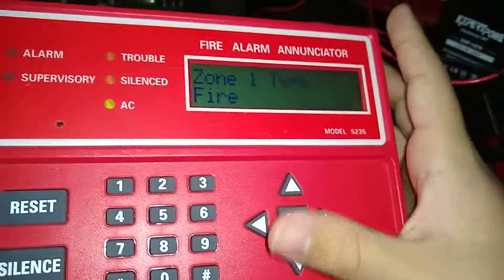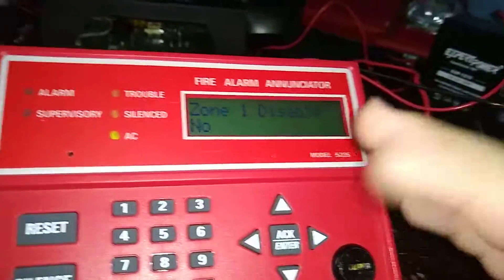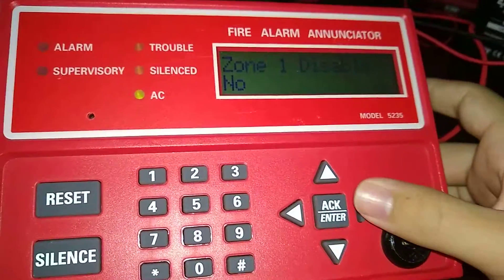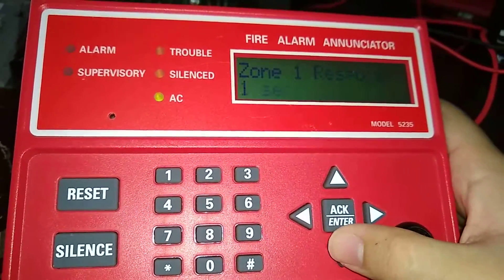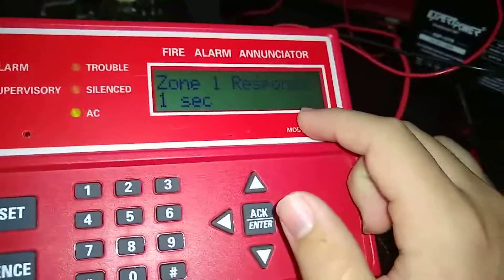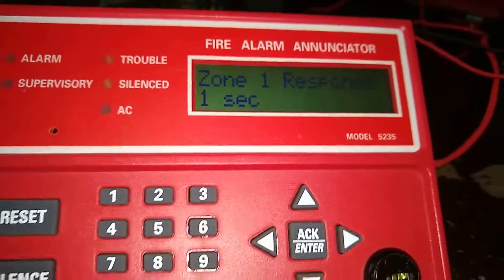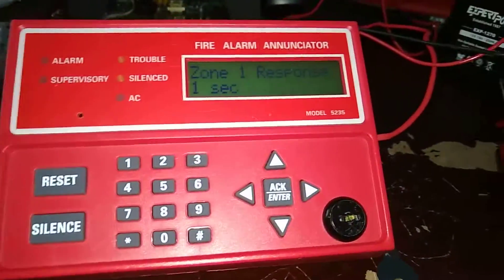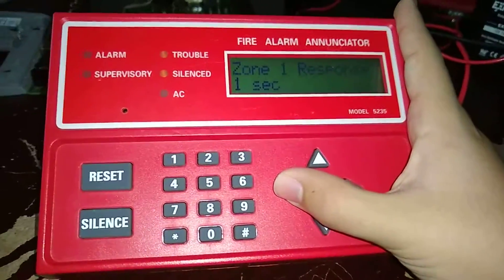Disabled — that is telling you: do you want this zone to be disabled? No, you don't want this zone disabled. If you do want it disabled, just use your arrow keys to scroll through yes or no. Zone one response — that is the response time. For example, if you hook a pull station up to zone one and program it to a one-second delay, the panel waits one second before going into alarm. You can go from one second to 40 seconds.